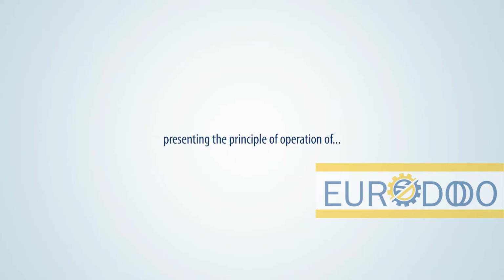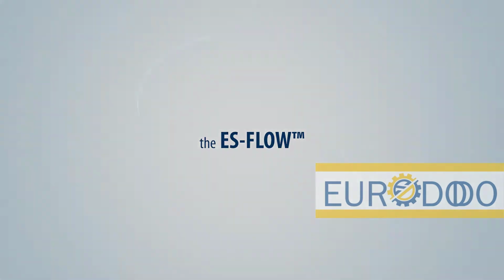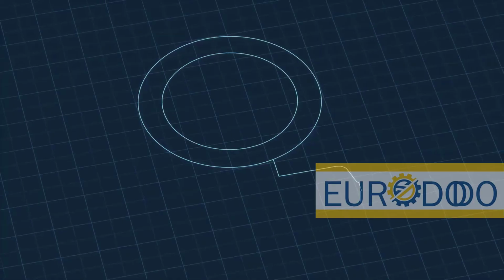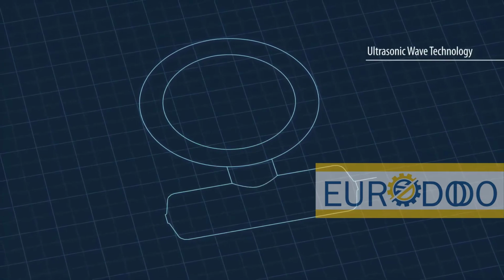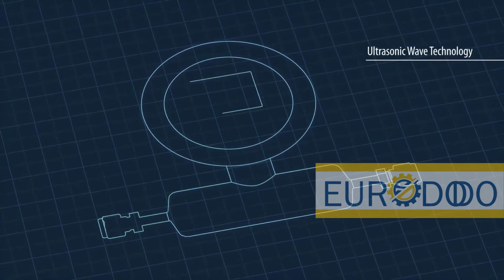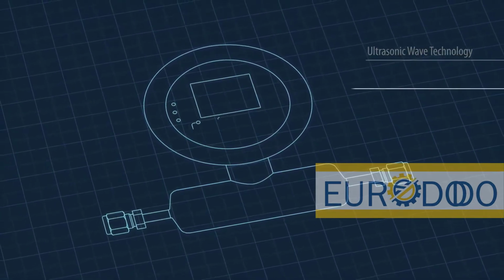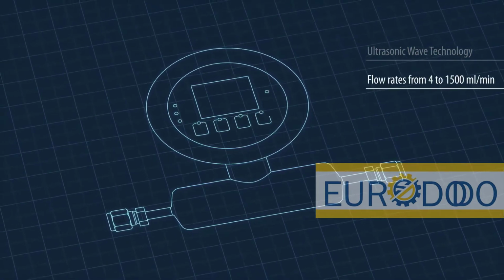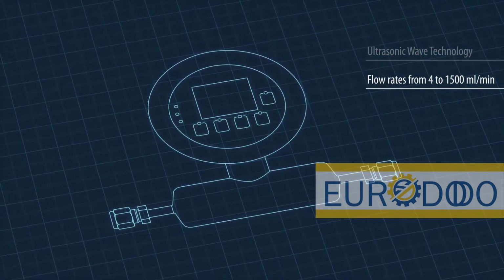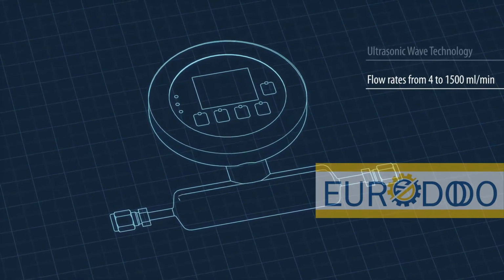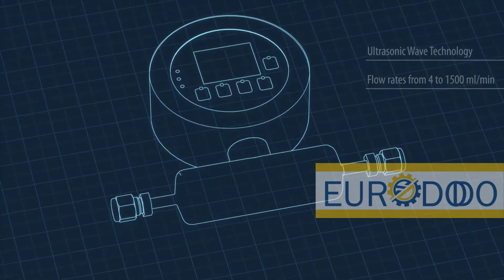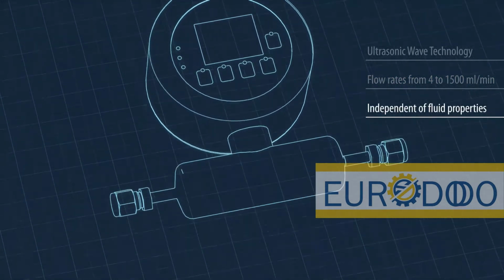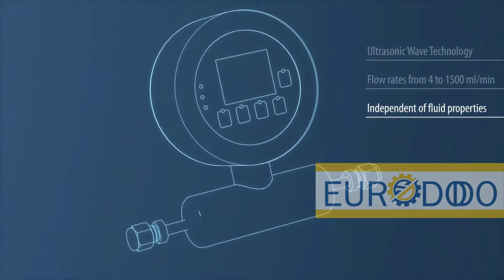Bronkhorst proudly presents the principle of operation of their new ultrasonic flow meters and controllers from the S-Flow series. Bronkhorst developed these revolutionary instruments using ultrasonic wave technology to accurately measure liquid flow rates as small as 4 to 1500 milliliters per minute. The unique ability to determine the actual speed of sound of the measured liquid makes the S-Flow independent of liquid properties and very easy to use.